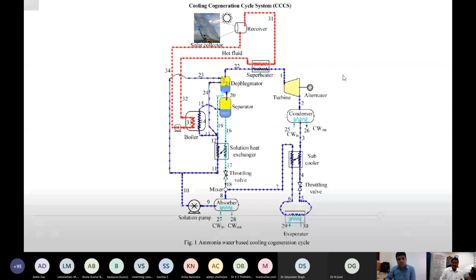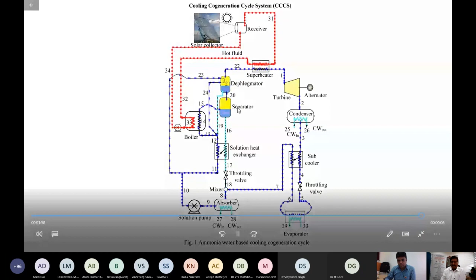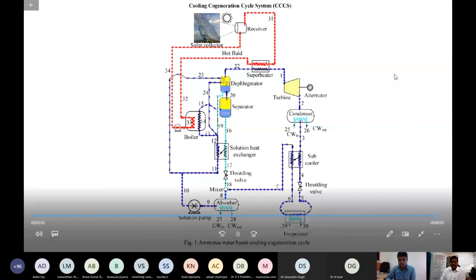But if two fluids are used, that is, a binary fluid system, the hot fluid temperature is decreasing, and in parallel the cold fluid temperature is also increasing continuously in the boiler, including evaporation. In the sensible heating and latent heating, the working fluid temperature is continuously increasing. So there is a close match between the hot fluid temperature and the cold fluid temperature. It will result in a minimum amount of entropy generation, where we can expect a minimum exergy loss. That is possible with this type of binary fluid system.